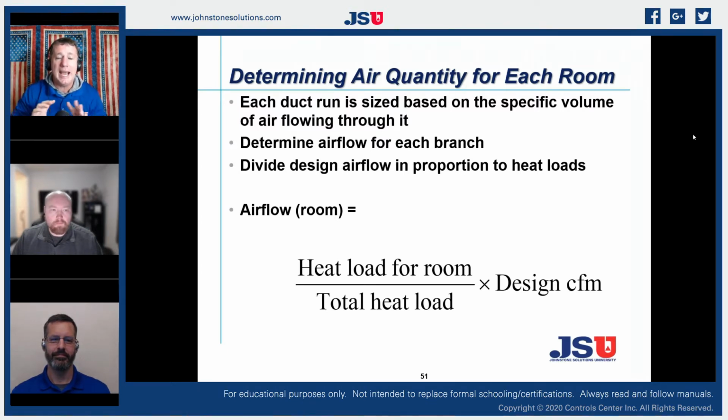Now, if we're looking at how to design our ductwork for our entire space, we're actually going to break it down per room. If we had done a true Manual J load calculation, it would give us a heat load for our structure. We would have also gotten a design CFM, which is typically based on air conditioning. Or if we have a heat pump, it's typically the same airflow for heating and for cooling. So we take our total heat load for our structure, which is a known, and our total CFM for our structure, which is also a known.